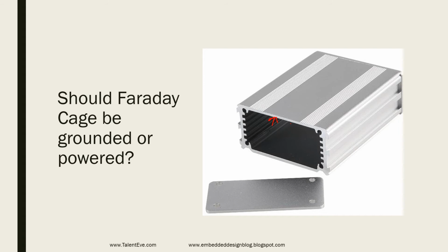Now here, what we are saying is, if the Faraday cage is left open and not earthed, the static charge might not have a path to leak, and this static charge may act as an ESD and cause failure to our electronic boards.